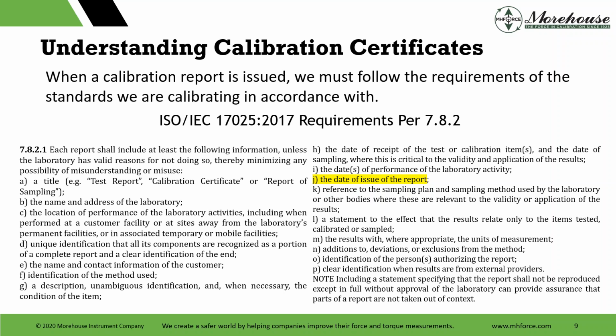And here, I have this section highlighted because it says the date of issue of the report. This is the section we missed. We try to get everything. Section J is where we recently got a deficiency, as we missed this one in the new standard. Really, we forgot to add it to the list of things that needed to be changed in our program, is what happened. So the current certificates we have now have the date of issue of the report. It is almost all the time the same as the calibration date.